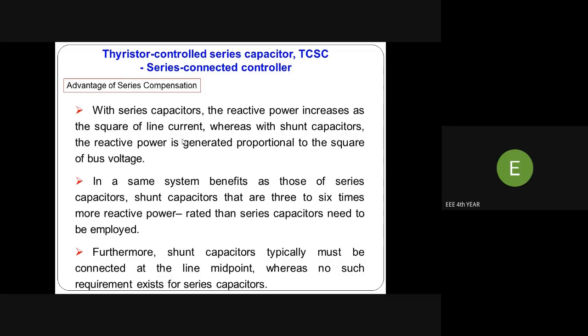The same system benefits as those of series capacitors require shunt capacitors that need to be applied with 3 to 6 times more reactive power than series capacitors. Furthermore, shunt capacitors typically must be connected at the line midpoint, whereas no such requirement exists for series capacitors. Shunt connected devices are connected at the midpoint of the transmission line, but that is not a requirement for series capacitors.